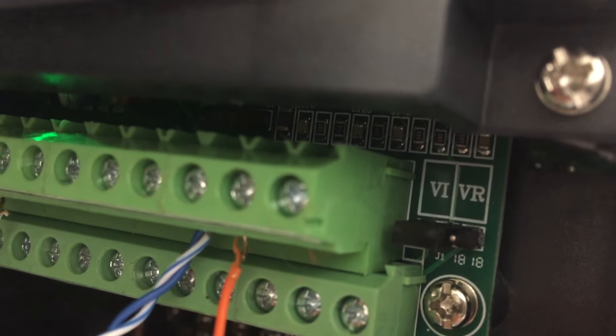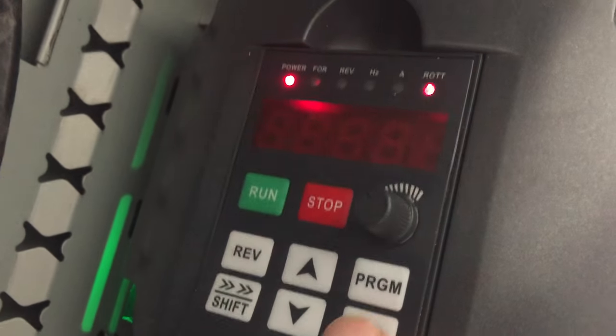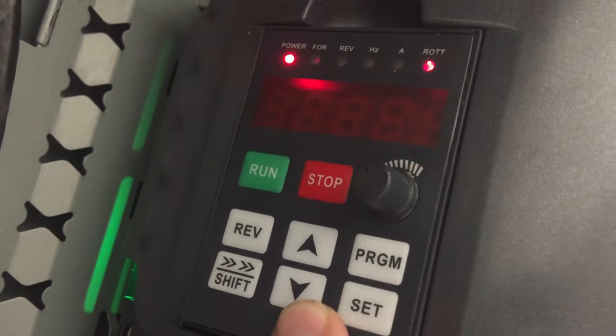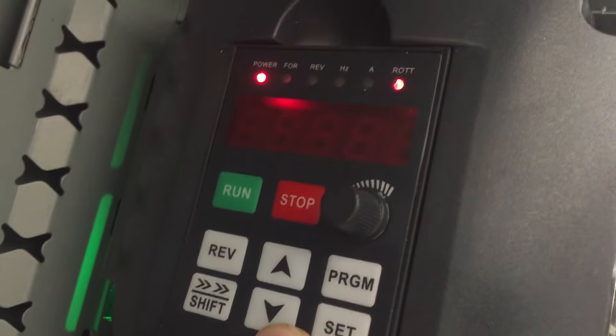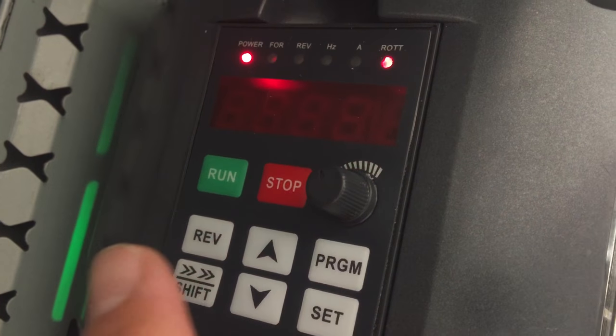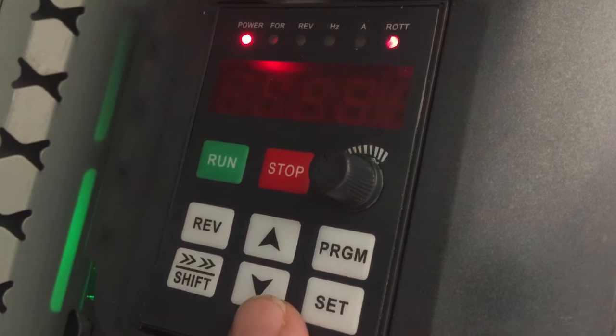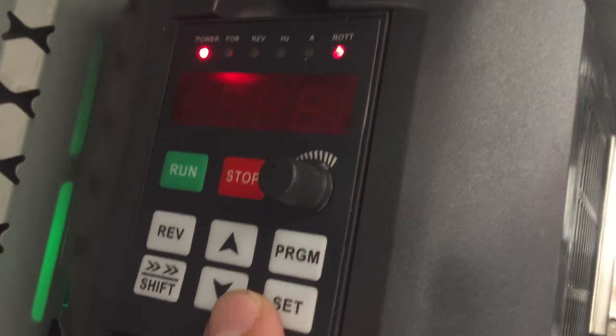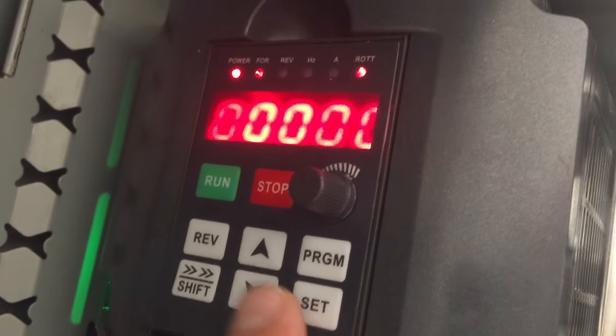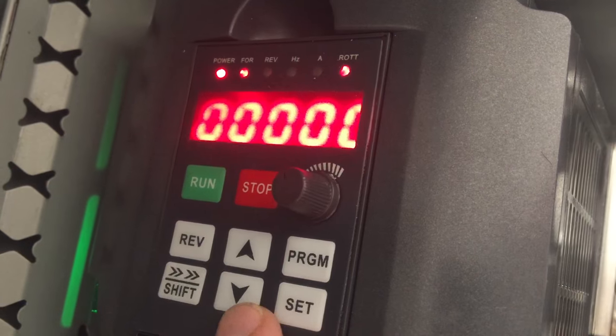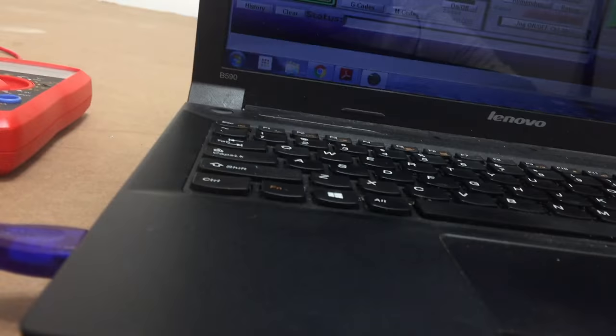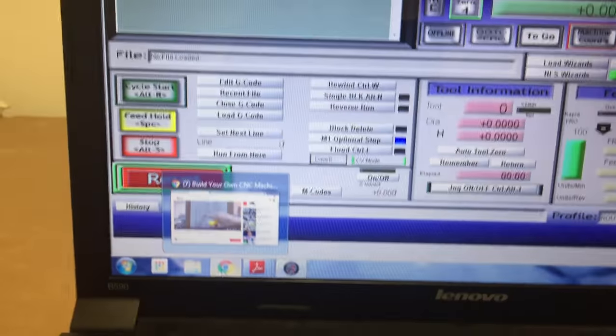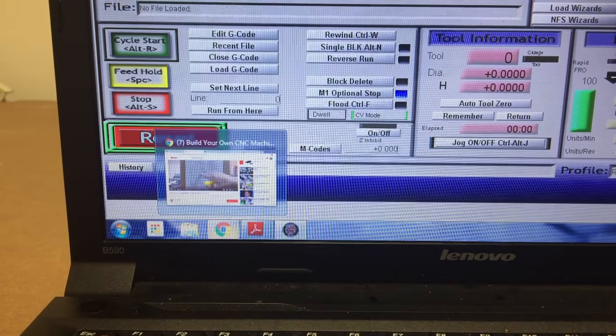On your settings, I don't really want to scroll through the screen here because it takes a while, but you need to have PD 001, I think it is, basically the second setting. PD 001 needs to be set to one, PD 002 needs to be set to one, and then you need to go to PD 0044, I believe. Let's see here, PD 044, and make sure that is set to one.